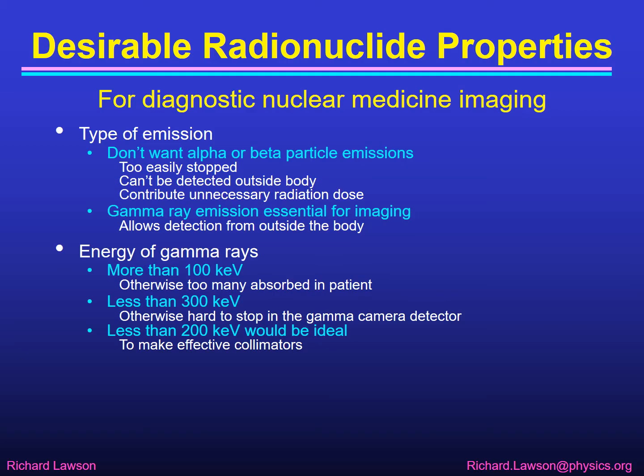The energy of the gamma rays is important as well. If the energy is too low there'll be too many absorbed in the patient, so an energy of more than about 100 keV will allow sufficient gamma rays to escape from the patient. However it needs to be less than about 300 keV, otherwise the gamma rays will be so energetic they will go straight through our gamma camera detector. In fact an ideal energy will be less than 200 keV otherwise it's too difficult to make effective collimators. So 100 to 200 keV is the ideal range, with 300 keV being really an upper limit.